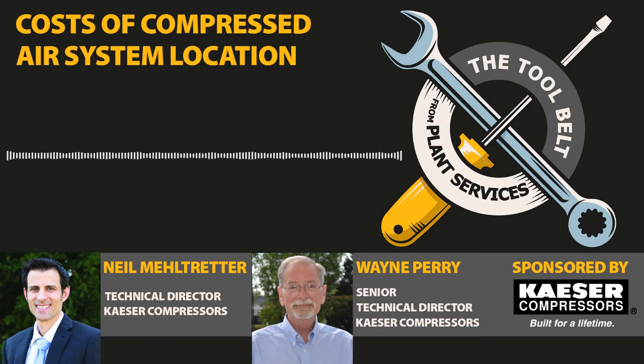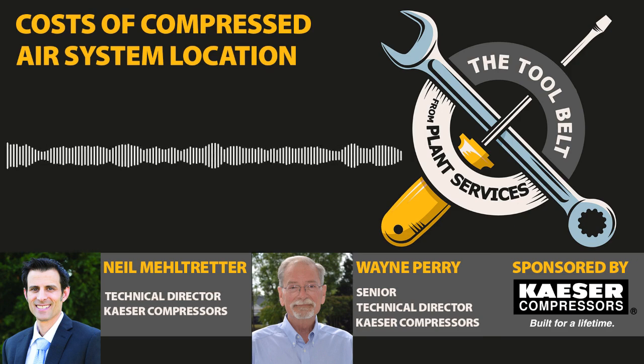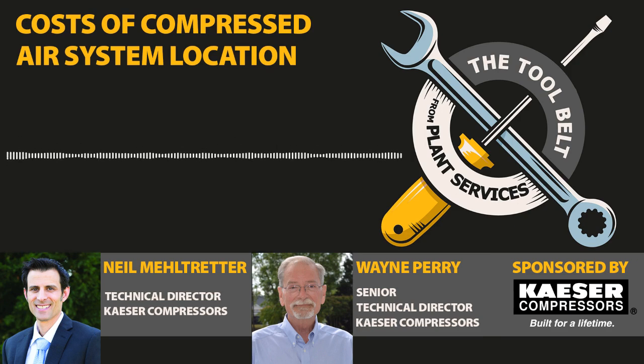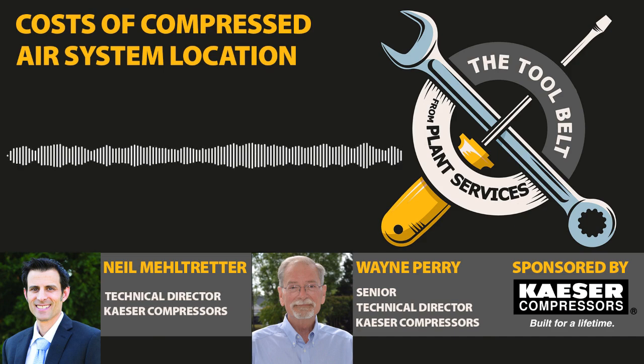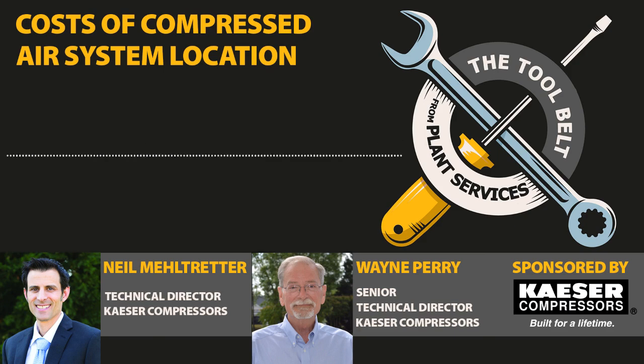I have seen variable speed compressors installed just below a place where they had to wash down their product. It was a food processing place doing clean-in-place, and the water came right down onto the compressor. In some cases, water on a compressor isn't all that terrible, but variable speed compressors have a lot of computer components. If you get any dust or moisture into those drives and circuit boards, they're going to die.